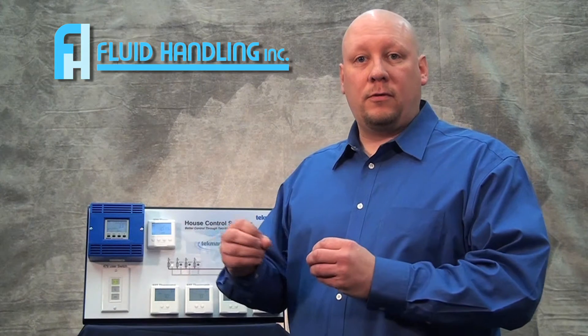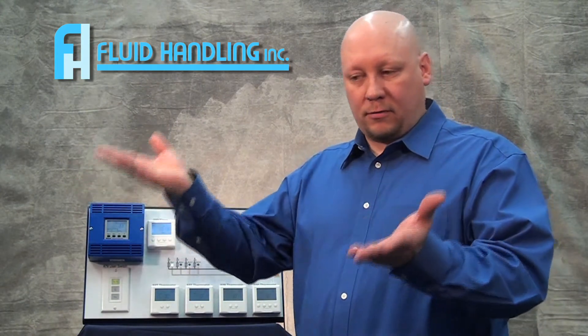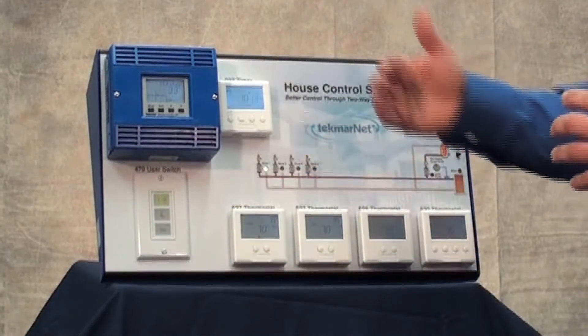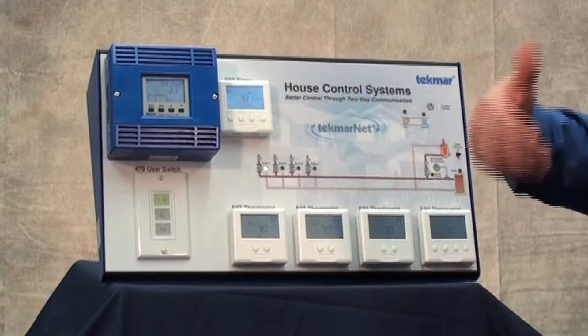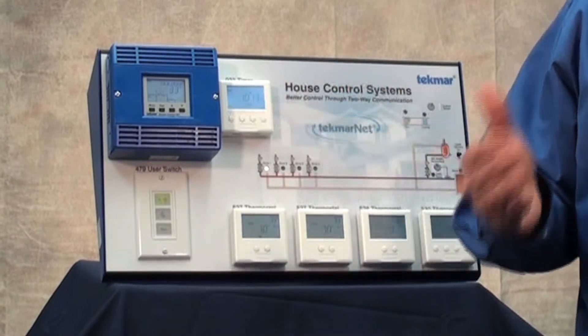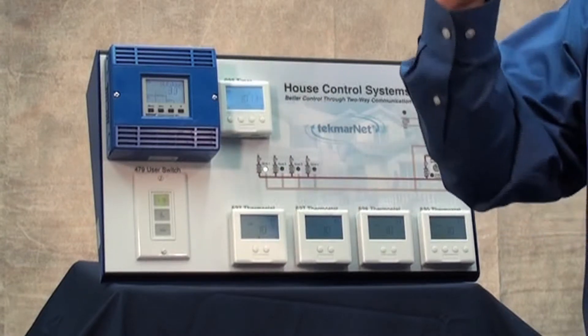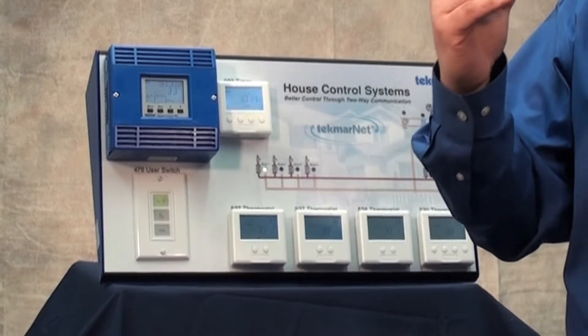What boiler manufacturers do, they all include an outdoor sensor now. You tell it a curve that when it drops five degrees outside, you might want to raise the water temperature two degrees being delivered to your system. But if it's dropping five degrees outside, but within the home we're not losing any temperature — we're maintaining — what tekmar is doing is looking at the thermostats, noticing we're not dropping in the home, and we're not going to raise that water temperature. We're going to only raise it when we can no longer maintain the set point within the home.